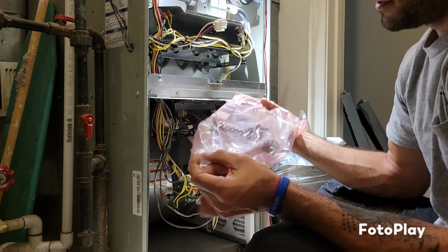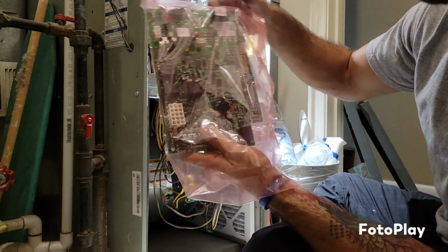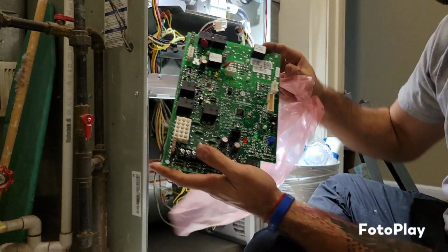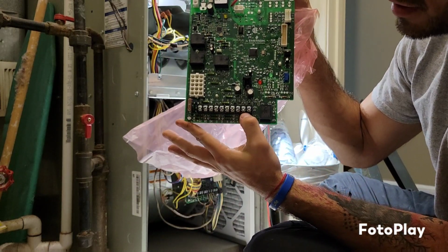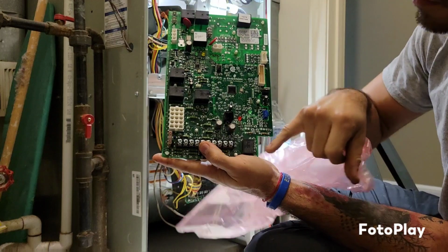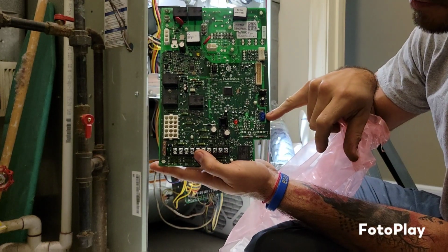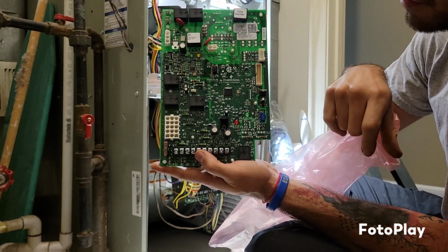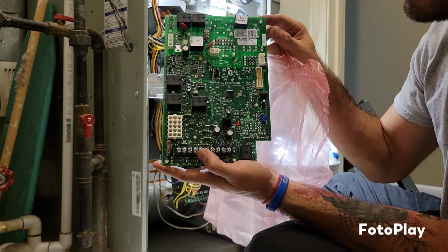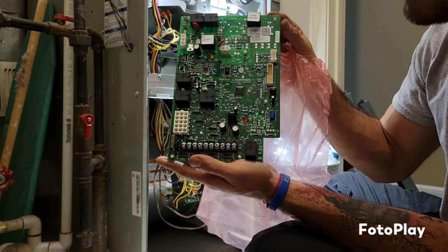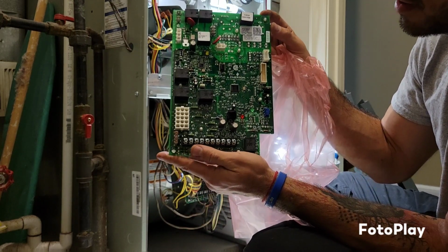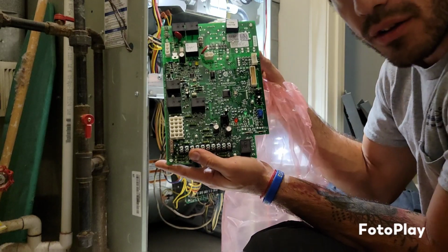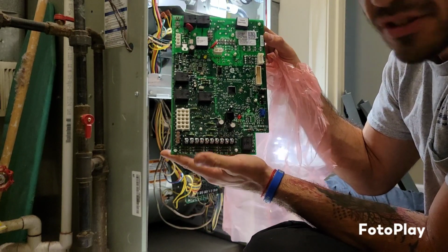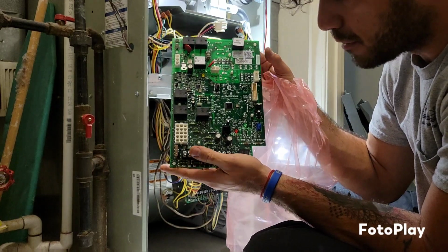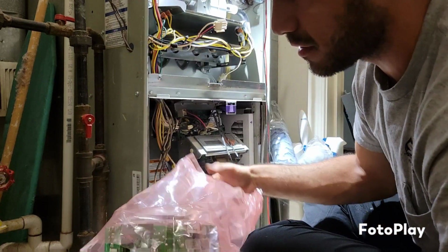So this is a new board right here, as you can see, pretty much identical to the old one. Obviously, you have your bottom terminals right here for your low voltage terminals, different relays. You have your chip for the algorithm. Then you have obviously the different prongs. You have your 24-volt fuse right here, and at this point we're basically just going to be plug and play. But then obviously we're going to go over everything else just to make sure that everything's matching up and lining up. So at this point, you're just going to watch me take this apart.